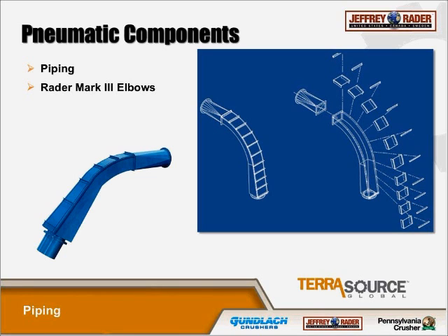As you can see over in this image, the high impact areas are easily removable and replaced. We also offer proprietary blends called R35 cast segments, which are extremely wear resistant. It's not an exact thing, but it will typically see 6 to 8 times the wear life of AR200. Kind of gives you a frame of reference. You don't want to be changing these things out very often. It's just more downtime, loses more money.